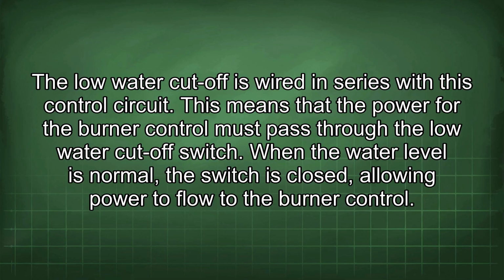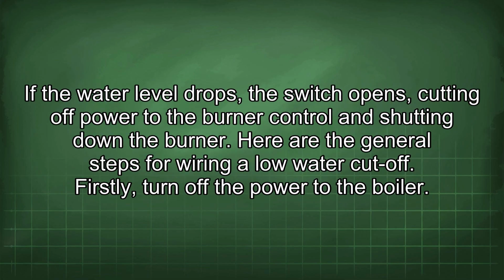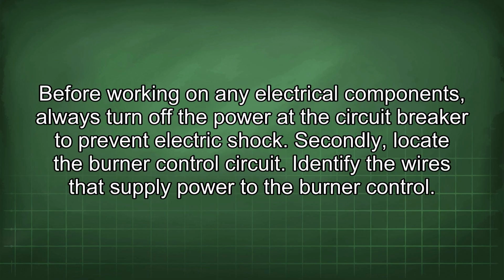When the water level is normal, the switch is closed, allowing power to flow to the burner control. If the water level drops, the switch opens, cutting off power to the burner control and shutting down the burner. Here are the general steps for wiring a low water cutoff. Firstly, turn off the power to the boiler. Before working on any electrical components, always turn off the power at the circuit breaker to prevent electric shock.